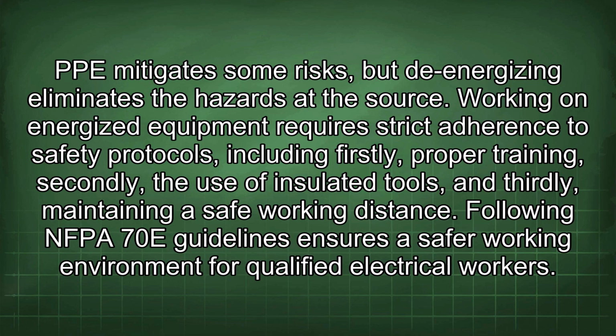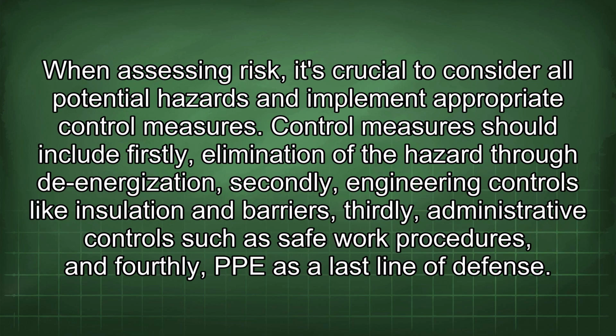Working on energized equipment requires strict adherence to safety protocols, including firstly, proper training, secondly, the use of insulated tools, and thirdly, maintaining a safe working distance. Following NFPA 70E guidelines ensures a safer working environment for qualified electrical workers. When assessing risk, it's crucial to consider all potential hazards and implement appropriate control measures. Control measures should include firstly, elimination of the hazard through de-energization, secondly, engineering controls like insulation and barriers, thirdly, administrative controls such as safe work procedures, and fourthly, PPE as a last line of defense.